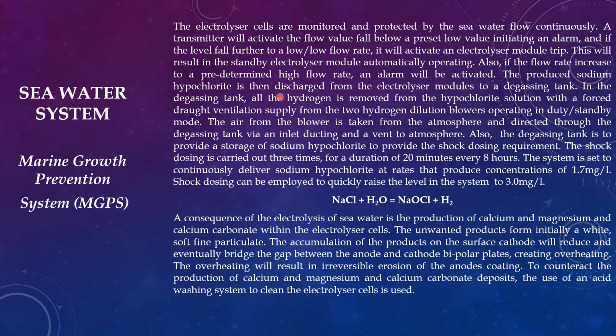The produced sodium hypochlorite is then discharged from the electrolyzer modules to a degassing tank. In the degassing tank, all the hydrogen is removed from the hypochlorite solution with forced draft ventilation supplied from two hydrogen dilution blowers operating in duty and standby mode. One fan will be on duty and the other on standby. The air from the blower is taken from the atmosphere and directed to the degassing tank via inlet ducting, and vented to the atmosphere after removing the hydrogen.